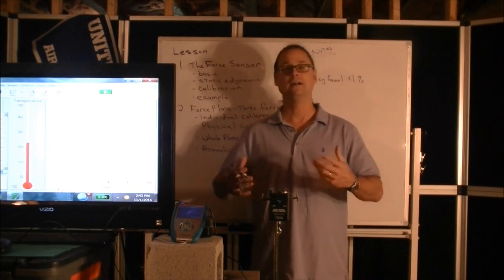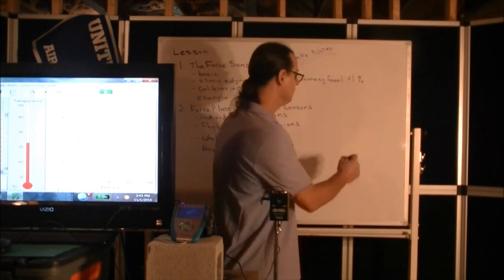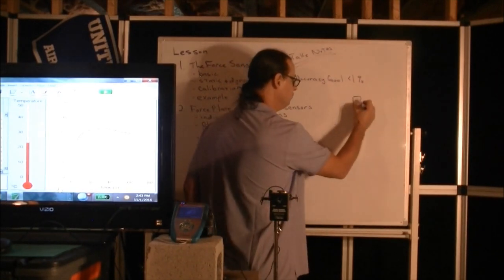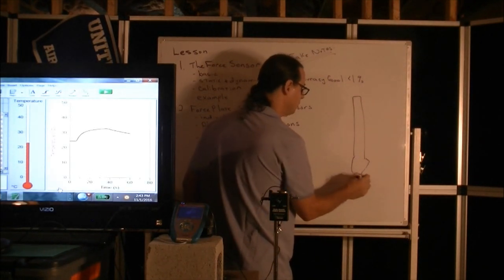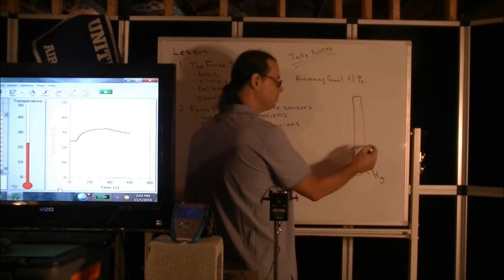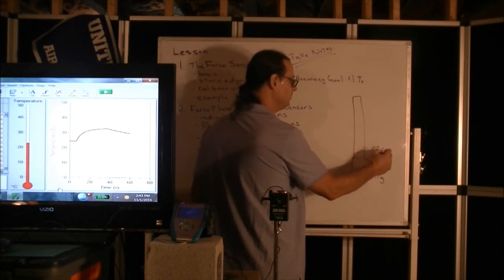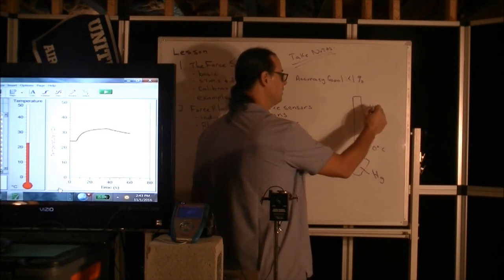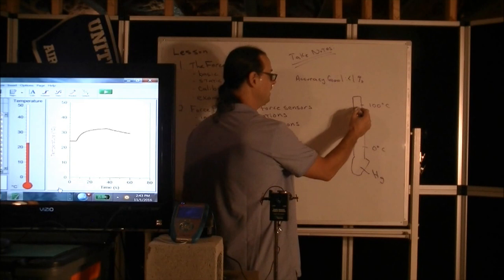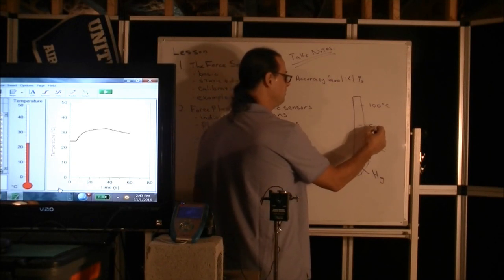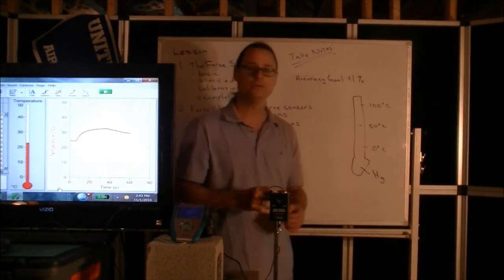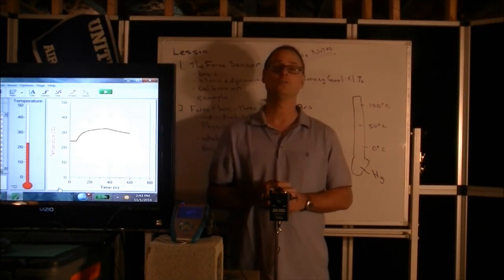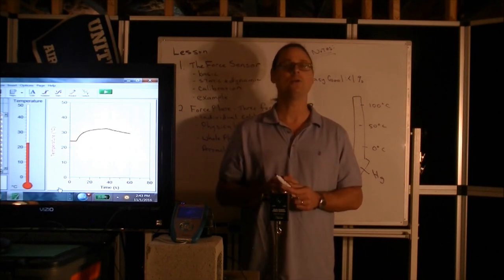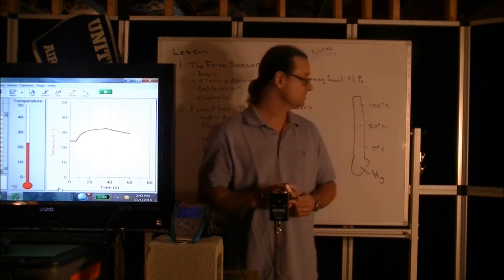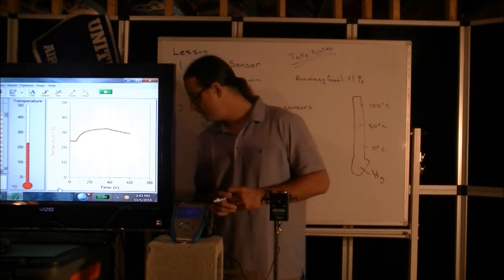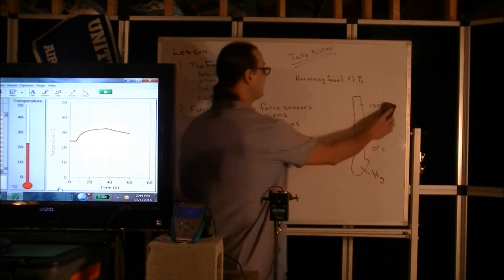And this is actually how old-fashioned glass thermometers were invented, right? They would take a glass tube, with the bulb at the end with the mercury. They'd submerge it in an ice water bath, and they'd mark that as 0 degrees Celsius. Then they'd put it in boiling water, and they'd mark that as 100 degrees Celsius. And the tick exactly in the middle would be 50 degrees Celsius. And then if you make 100 evenly spaced tick marks along the way, you've essentially calibrated that thermometer to 1 degree Celsius. So that's the general idea of what we're trying to do anytime we're talking about calibration.